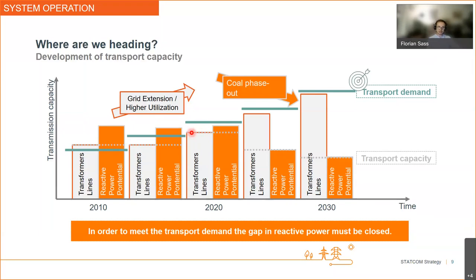But then we started a lot of grid extensions. We also came up with ideas like higher utilization of the system, curative actions, for example, high temperature lines. So we were increasing step by step the thermal transfer capacity, which brings us to the year 2025 and even 2030. So you can see the transformers and lines, they're really close to the transport demand. They're not the limiting factor anymore.